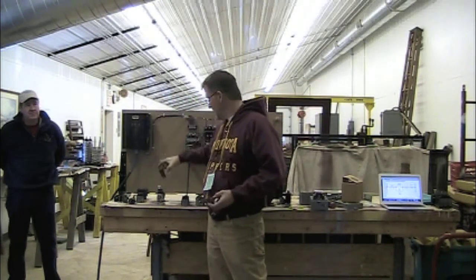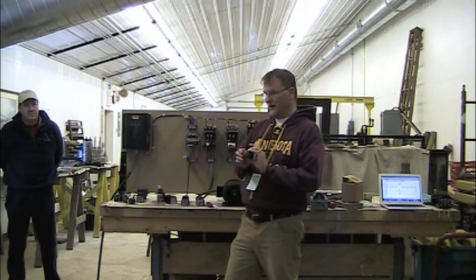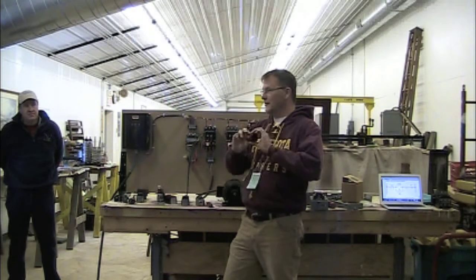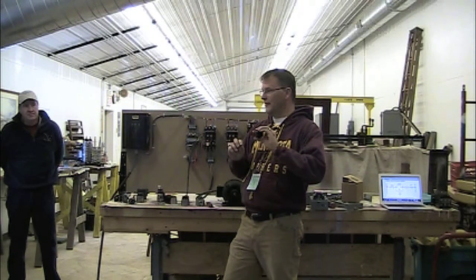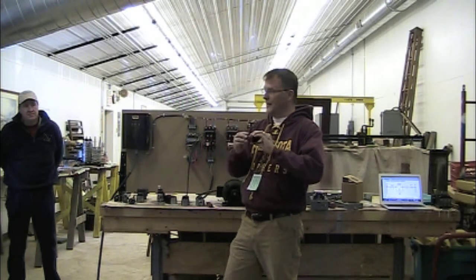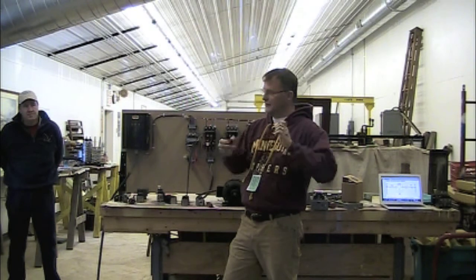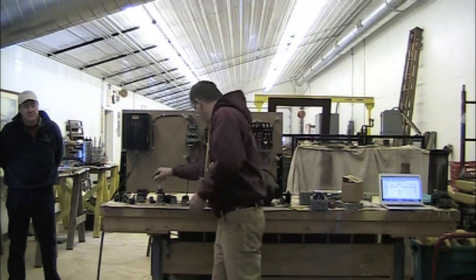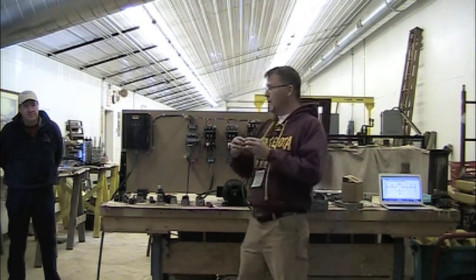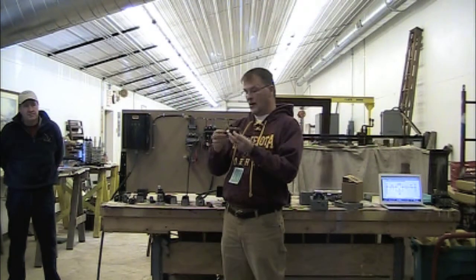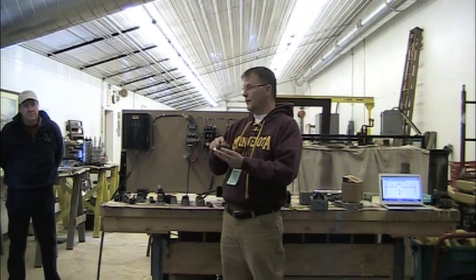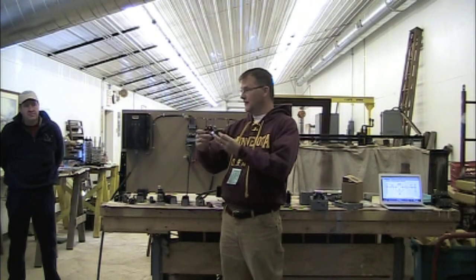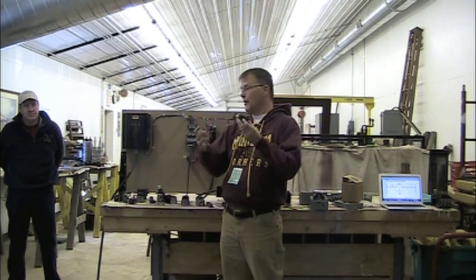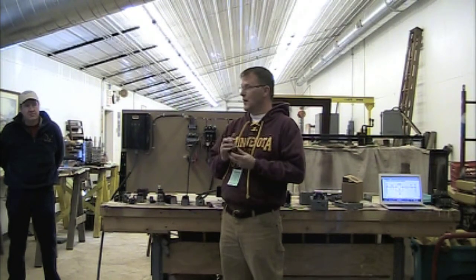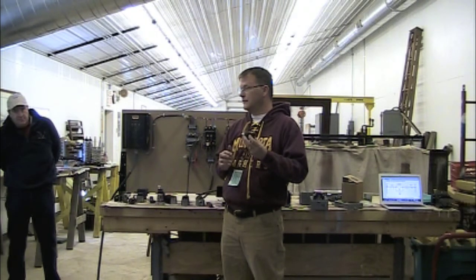Yeah, normally closed. Okay. You've got to be careful on the maintained ones, since they're not a momentary thing, as to what you get and what the operation is. That one's actually busted. There's a state when it's pulled out and when it's pushed in. So when it's pulled out is the state of what these are for a momentary one. If it's a normally closed contact, then it's closed when this is out, which is probably what you want for an emergency stop, because you want to hit the button and open the contacts.